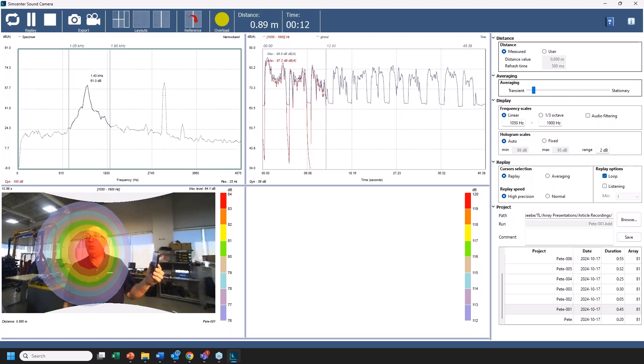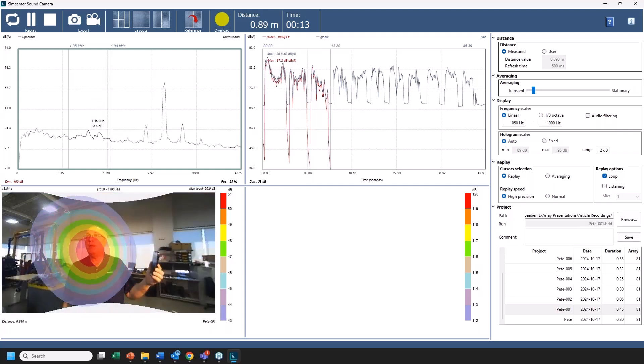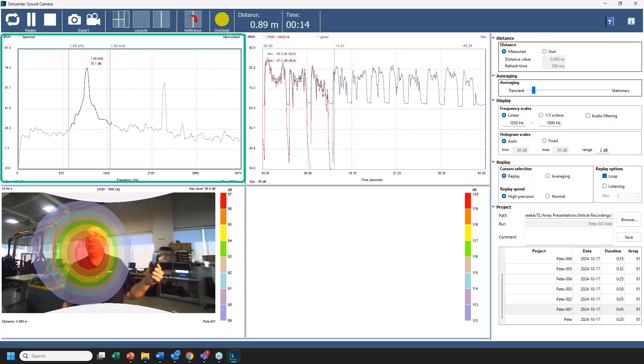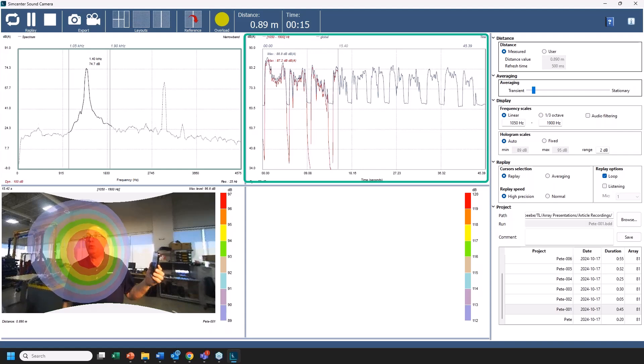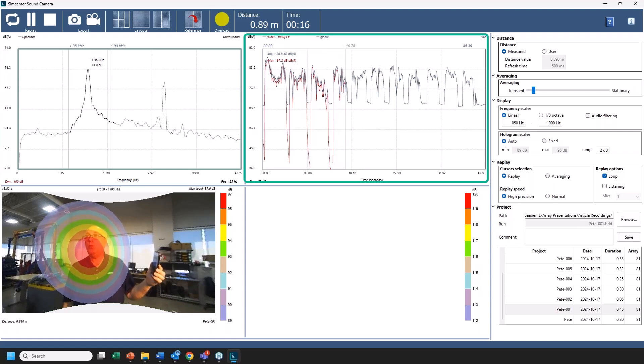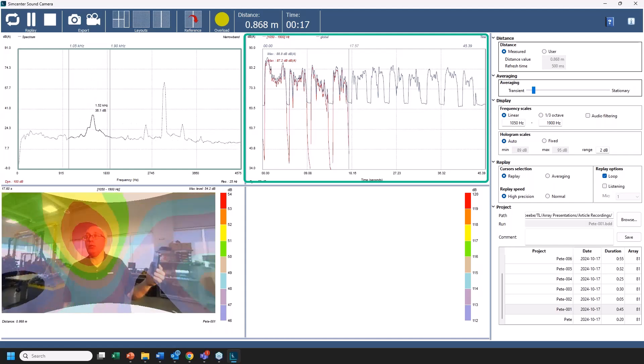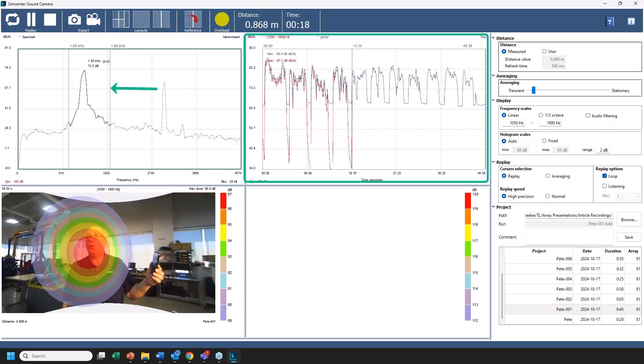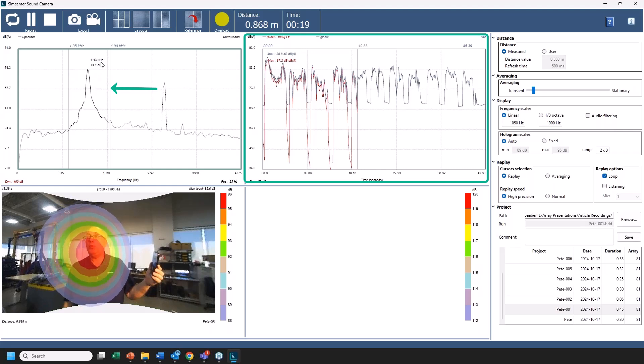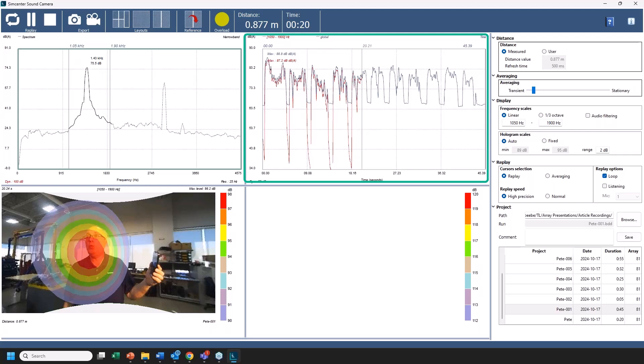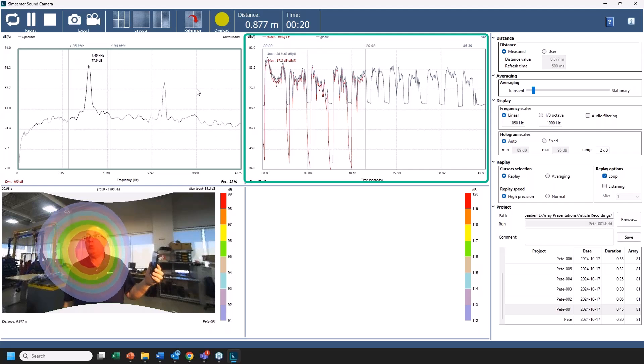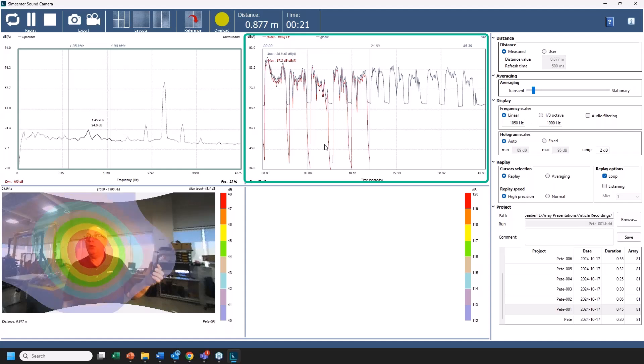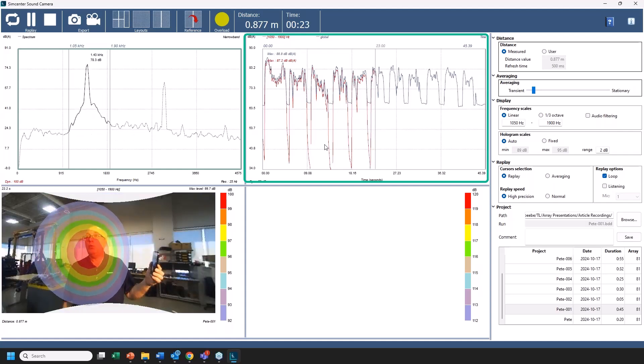So we have four displays here. As you can see, the upper left display is live FFT. The upper right display shows the overall sound pressure level over time, and the red line that's being traced comes from where I have this double cursor here. I've selected a frequency range of approximately 1000 hertz to almost 2000 hertz. So the blue line is all the frequencies and the red line is just the frequencies between the cursors.